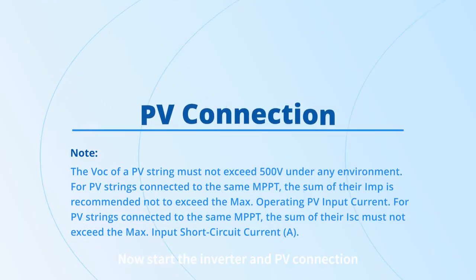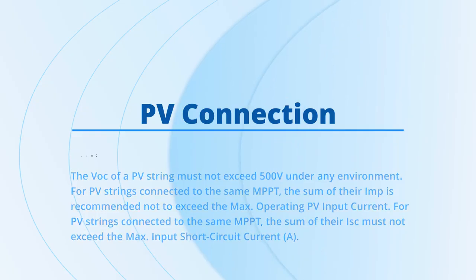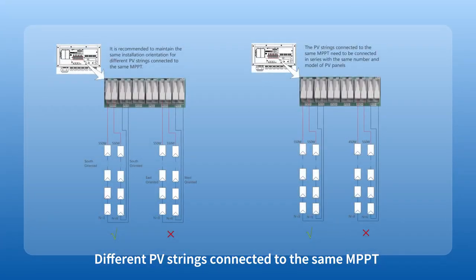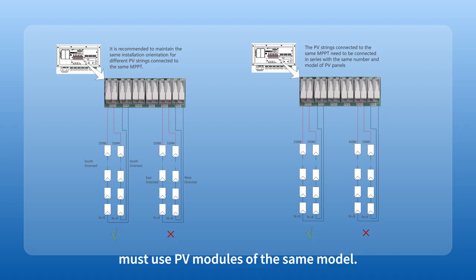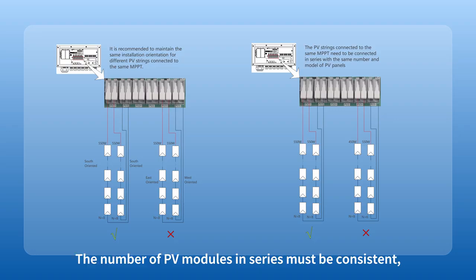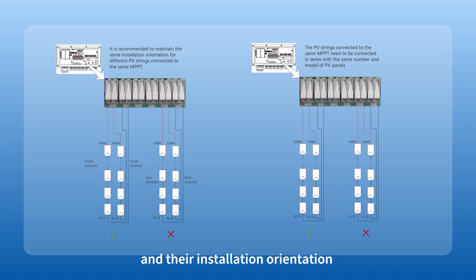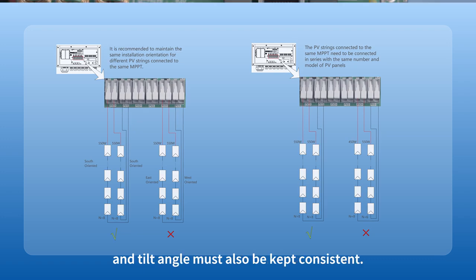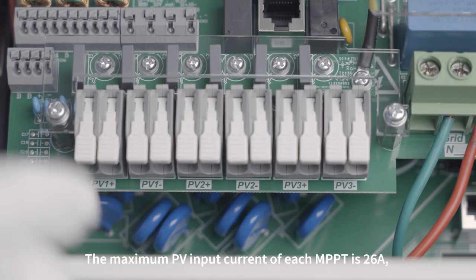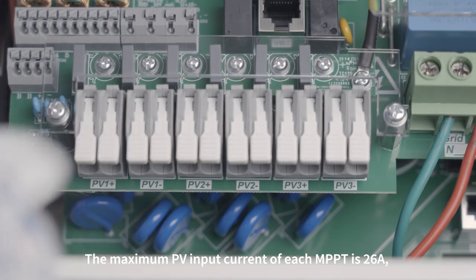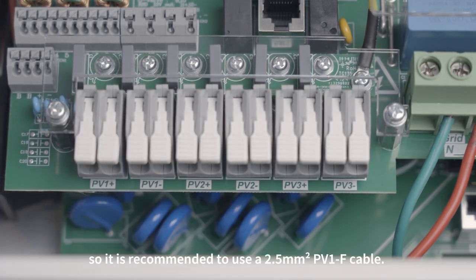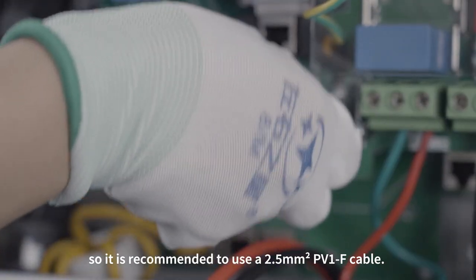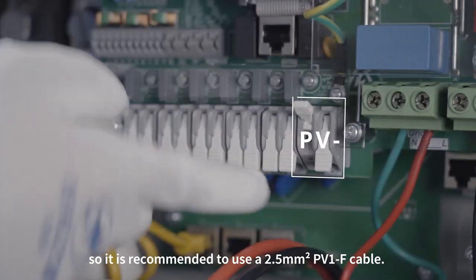Now start the inverter and PV connection. Different PV strings connected to the same MPPT must use PV modules of the same model. The number of PV modules in series must be consistent, and their installation orientation and tilt angle must also be kept consistent. The maximum PV input current of each MPPT is 26 A, so it is recommended to use a 2.5 mm squared PV1F cable.